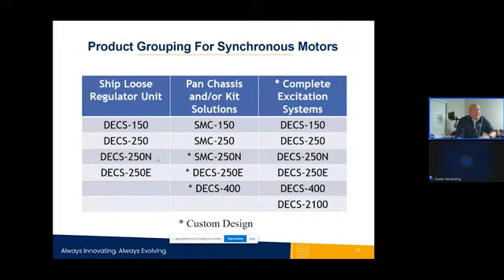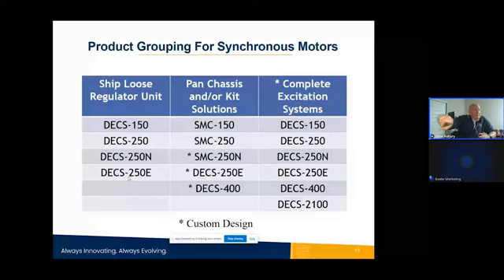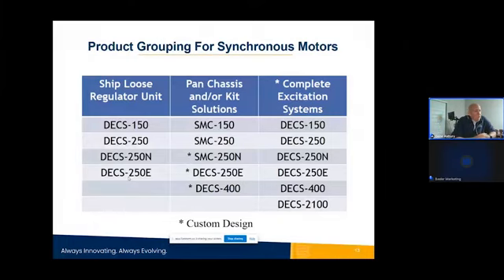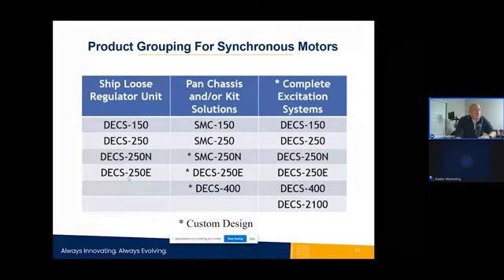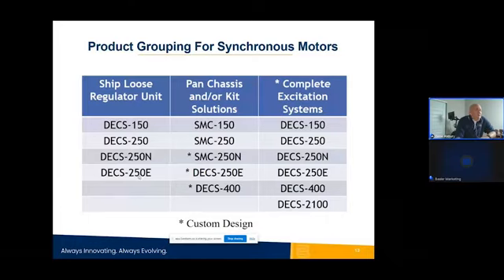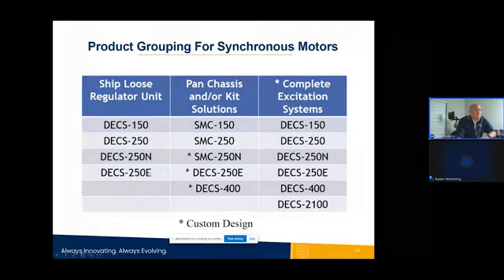The DECS-250E basically takes the controls from the 250 and provides a bias signal to a 3 SCR bridge that gives us up to 200 amps of excitation. The 250E is ideal for slip ring motors that require much more field current than the brushless excited motors. So we've had a lot of success with the 250E on slip ring motor applications.